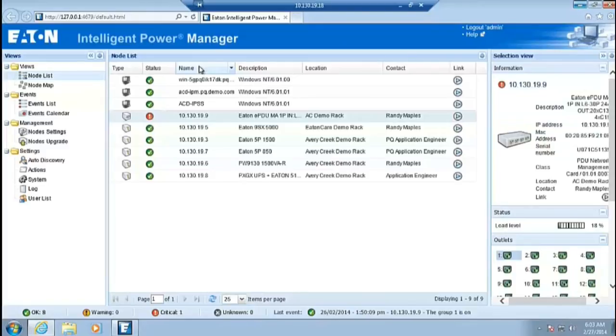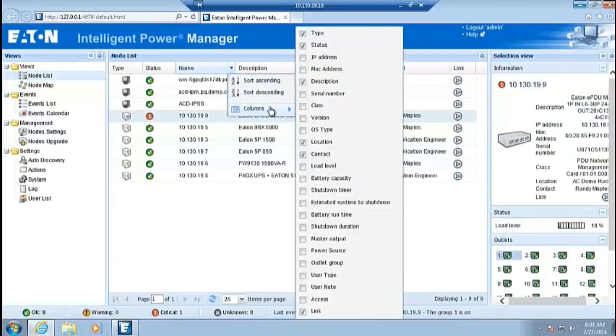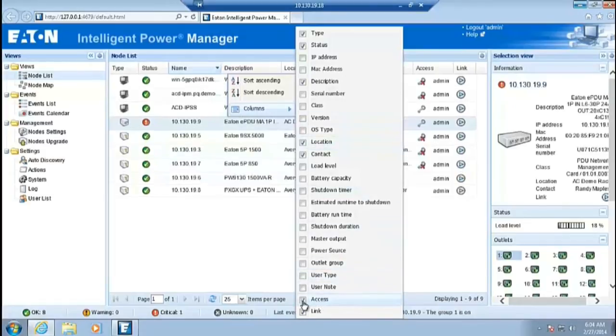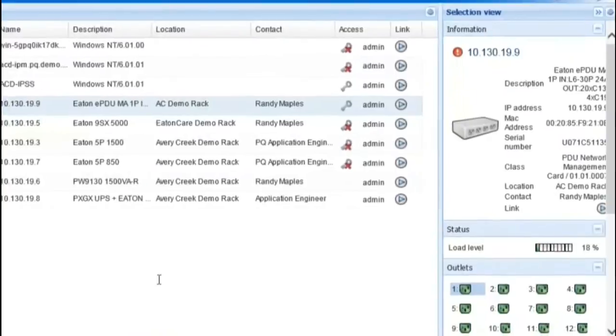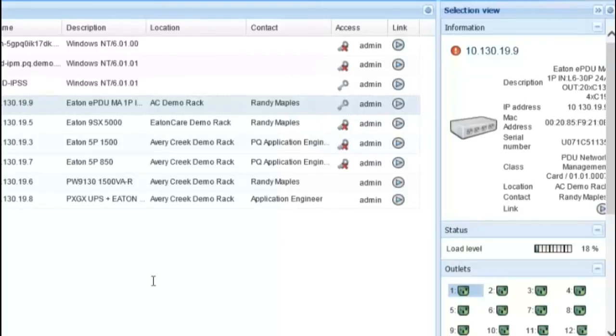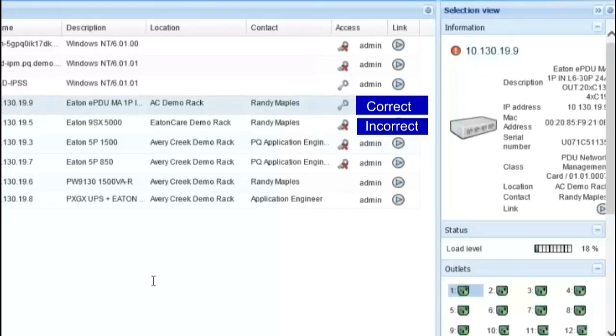Hover the mouse over any of the headers in order to engage a drop-down menu. Click on the drop-down arrow provided in order to open the menu. Hover the mouse over the Column option. Locate the Access option and place a checkmark in the box to the left. Once checked, the Access column will appear within the node list. The Access column will allow visibility to determine whether or not the nodes are linked correctly. Correctly linked nodes will generate a key icon, while nodes linked incorrectly will generate an X over the key icon.